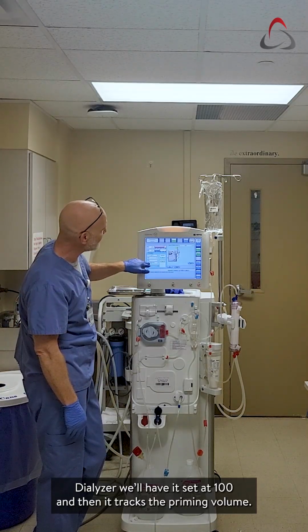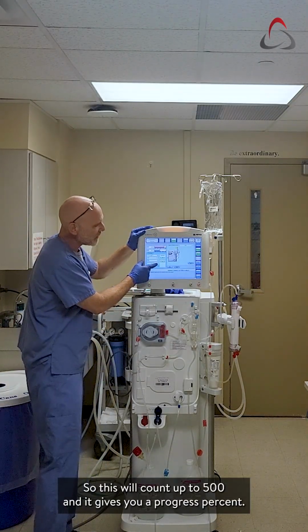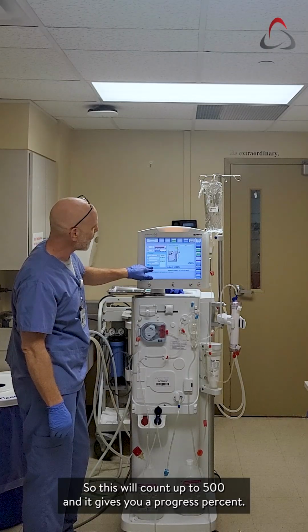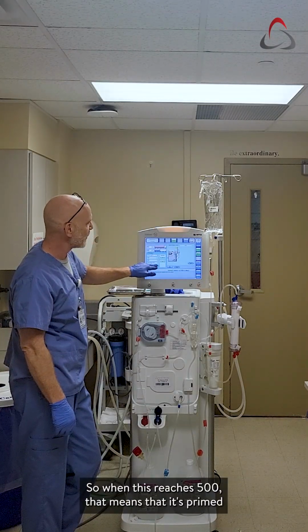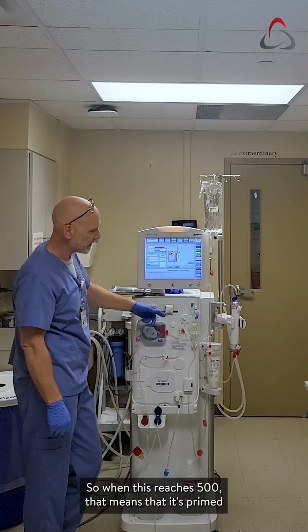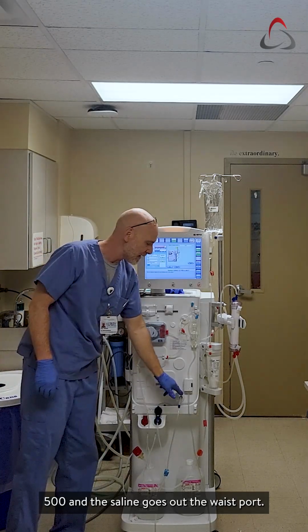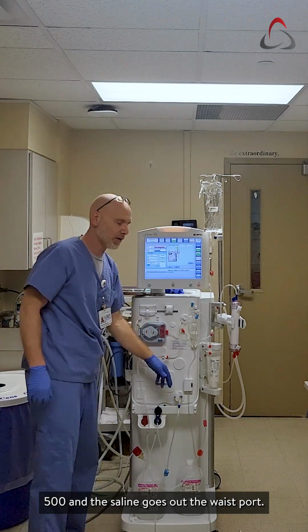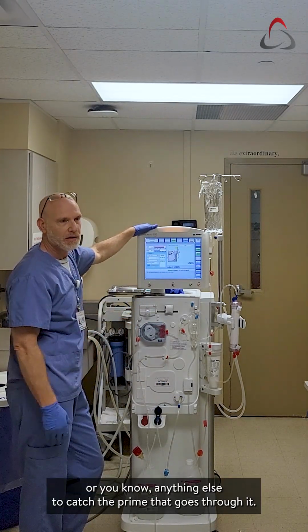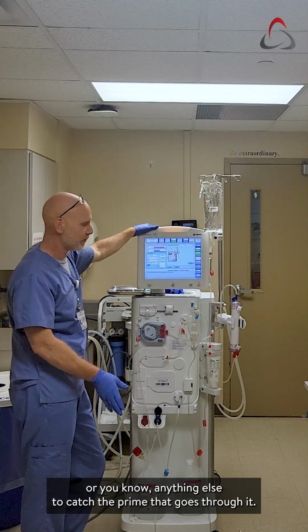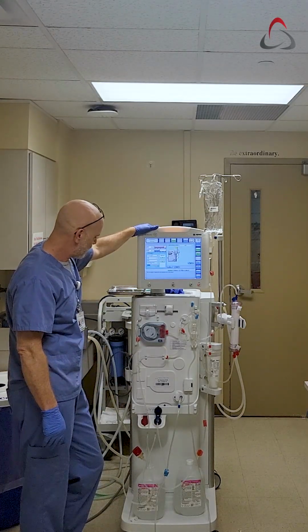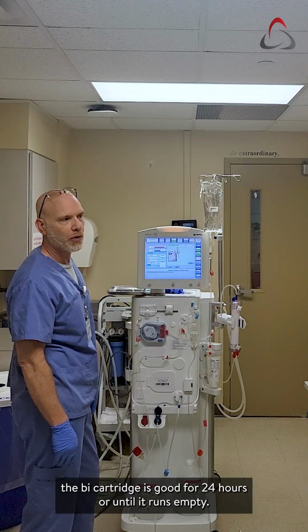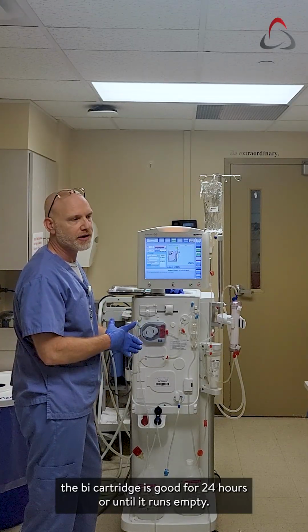And then it tracks the priming volume, so this will count up to 500, and it gives you a progress percent. So when this reaches 500, that means that it's primed 500, and the saline goes out the waste port. So you don't need a priming bucket or anything else to catch the prime that goes through it. The bicarb cartridge is good for 24 hours or until it runs empty.